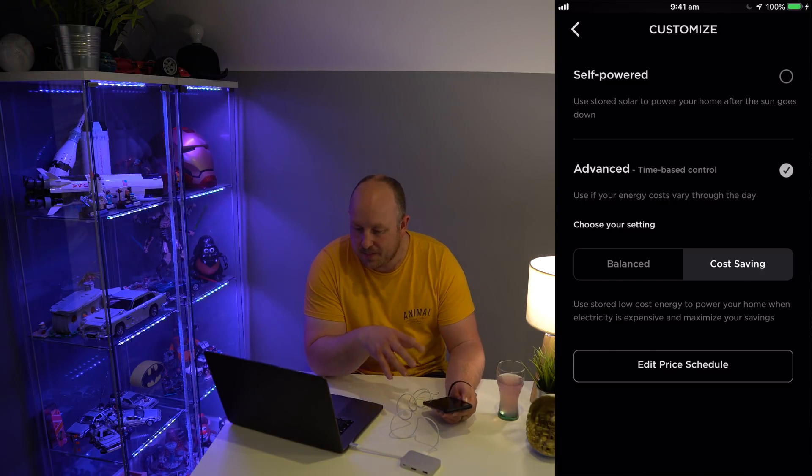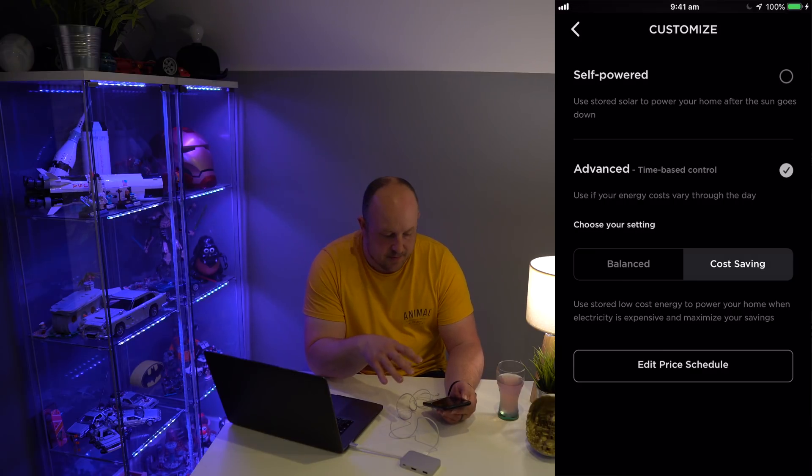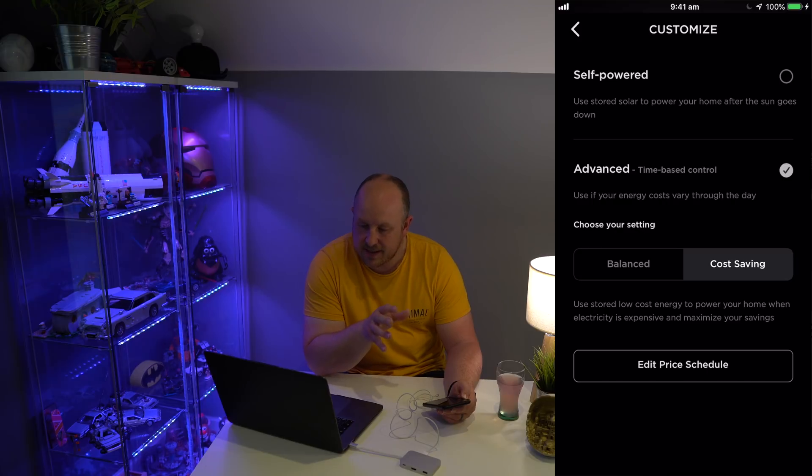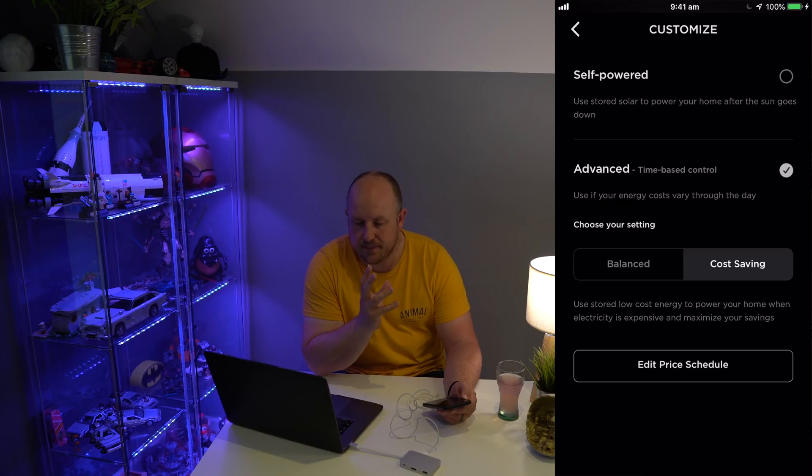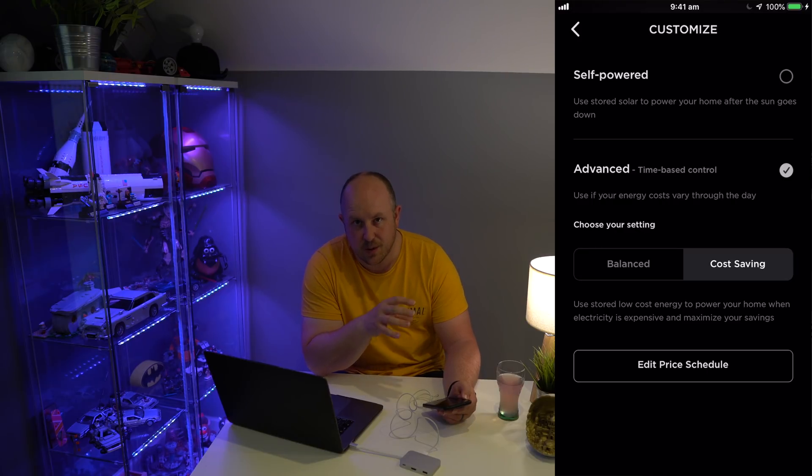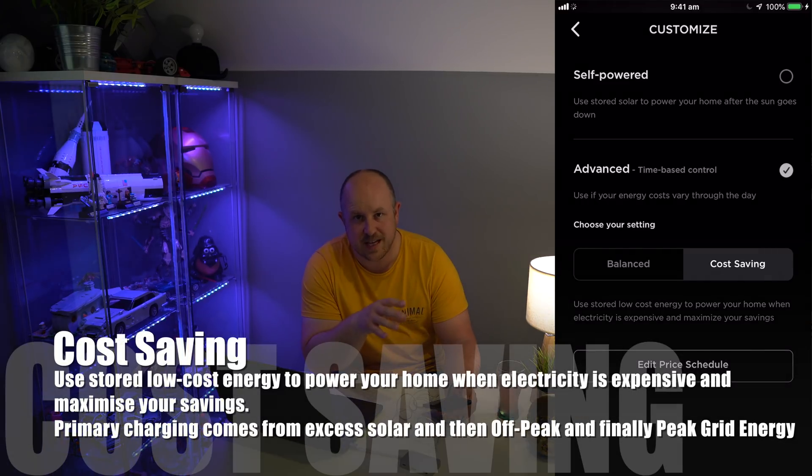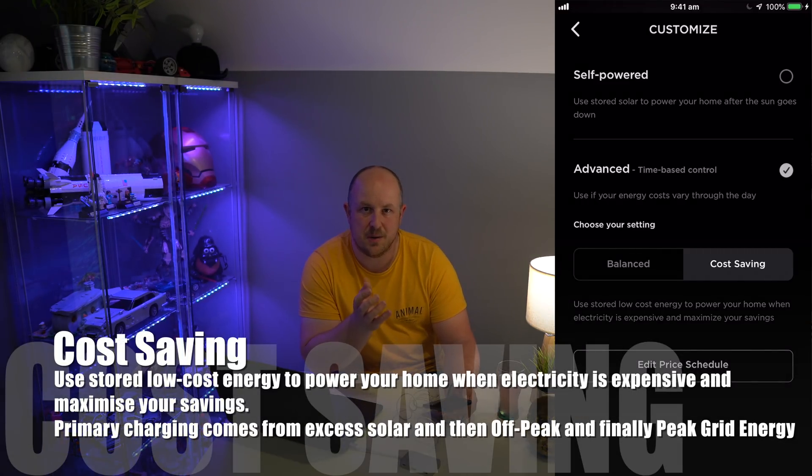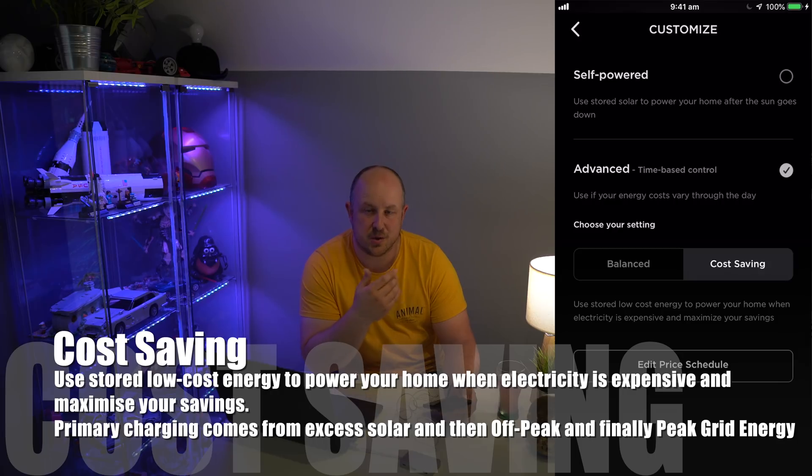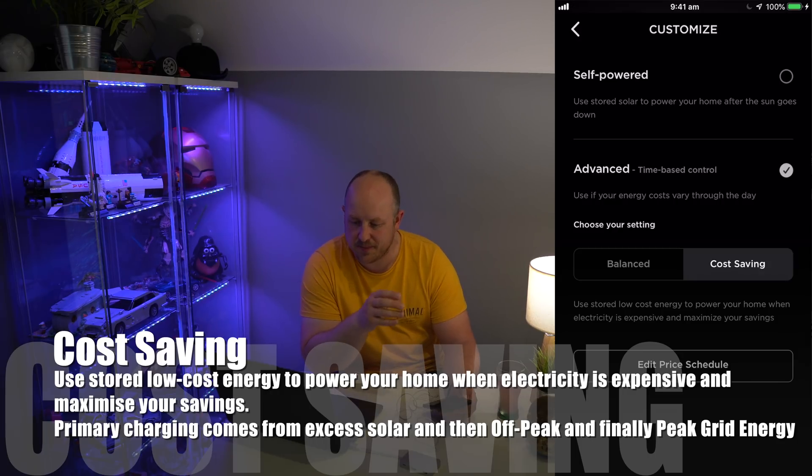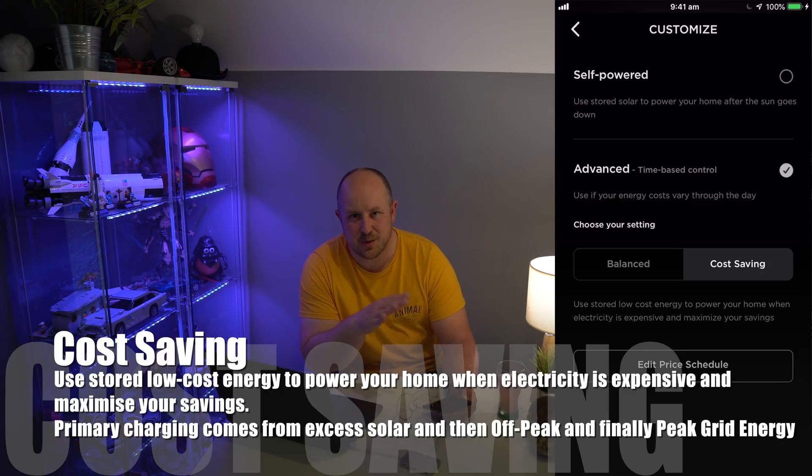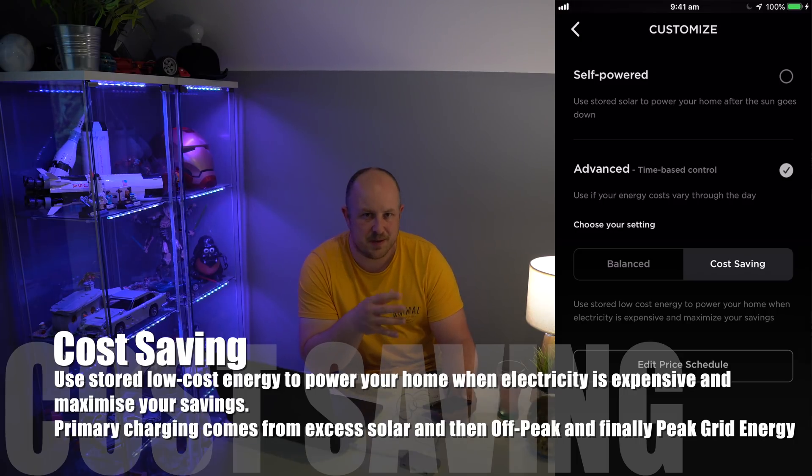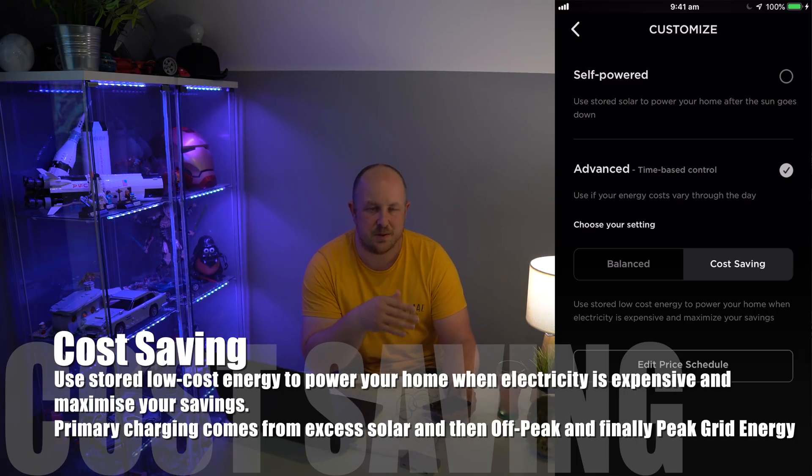If you have Cost Saving set up, the priority works as follows: the priority is to utilize solar as much as possible. If the sun is out, your Powerwall will go into charge or standby mode and utilize solar as much as possible, balancing out based on how much solar you're getting and how much your house needs.